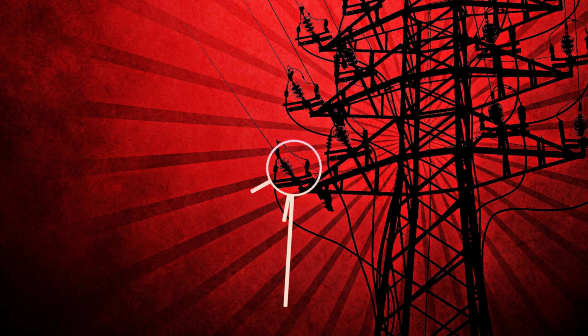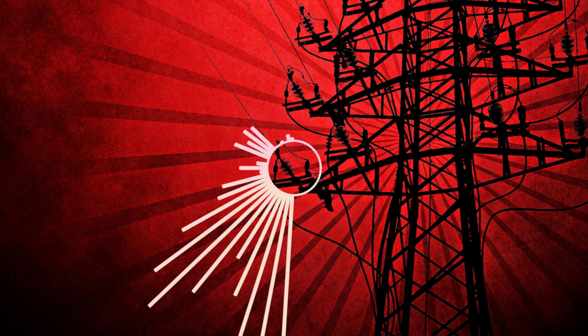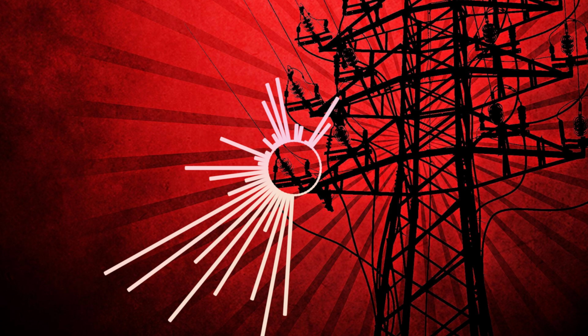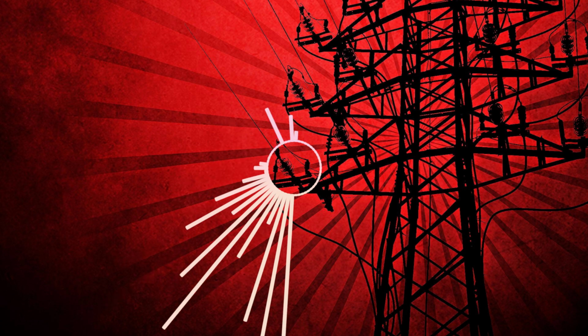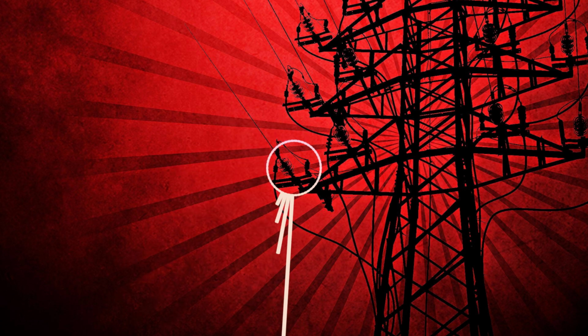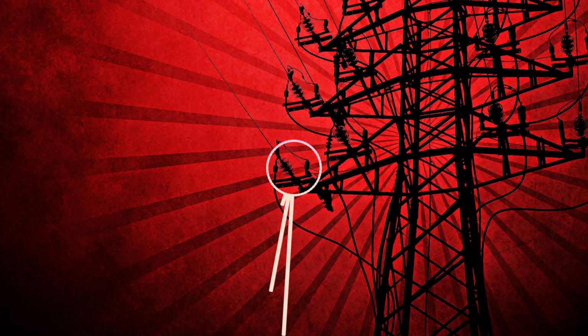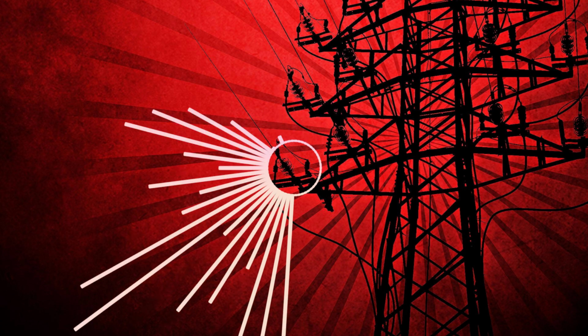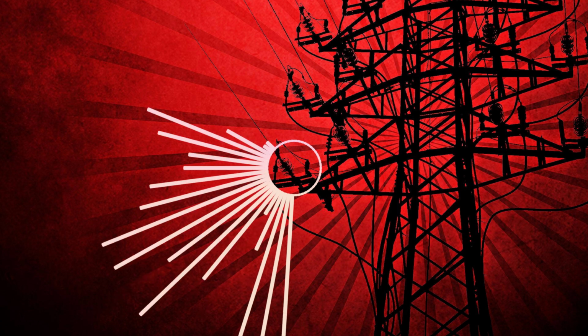In short, arc flash hazards are dangerous bursts of energy that can cause severe injuries or death. Article 110.16 requires electrical equipment to be marked with a visible warning label that alerts workers to the risks of an arc flash if they are working on the equipment while it is still energized. The warning is meant to keep workers safe by ensuring they are aware of the danger and can take necessary precautions before working on the electrical equipment.